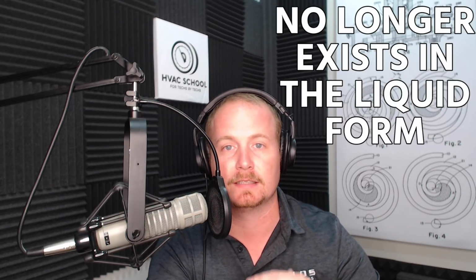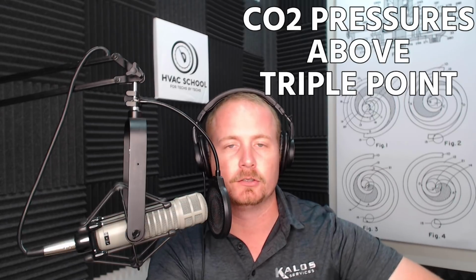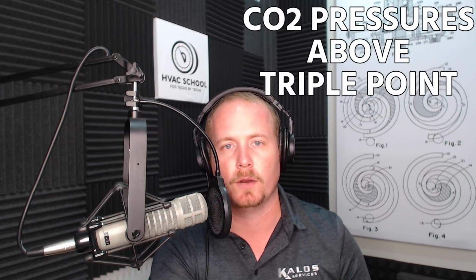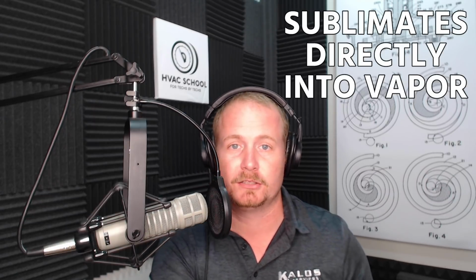So a few things you need to know about CO2 is, first off, it has something called the triple point, which is the lower threshold on CO2 where it no longer exists in the liquid form. So we have to keep CO2 pressures above the triple point, which is why you often hear him talking about charging with liquid and making sure it doesn't change to a solid. So for example, CO2 at atmospheric pressure, we call that dry ice. It goes directly from dry ice and sublimates directly to a vapor.